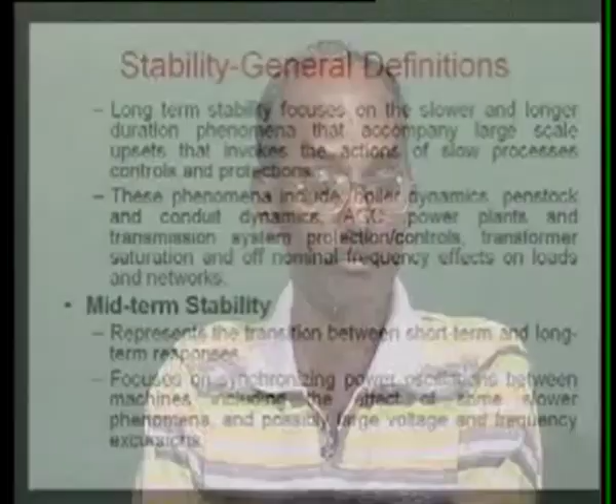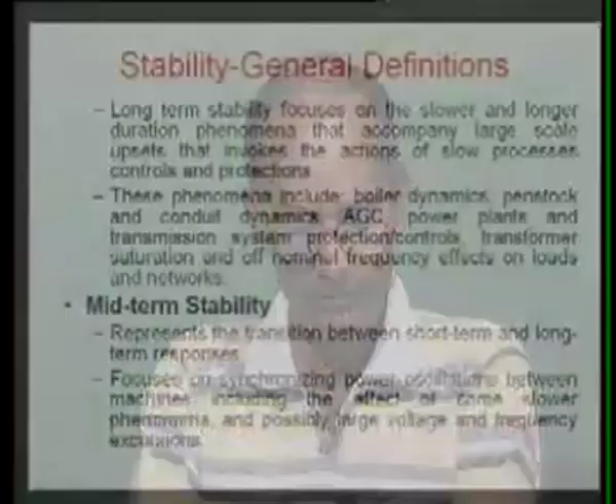This phenomena includes boiler dynamics - all the mechanical devices you must be very careful about. All mechanical devices including governors, boilers, penstocks, conduit dynamics, have high time constants, large compared to the electrical system.